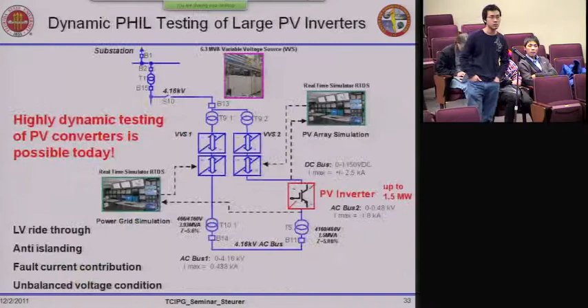If you utilize standard protocols that the utility community uses, and RTDS has provided interfaces for, such as DNP, Modbus, or 61850, then it's a matter of getting the respective I/O cards for the RTDS and having the counterpart in the real-time network simulator. We also experiment with customized protocols developed on dedicated FPGA platforms that tie seamlessly into the RTDS. I think the interface is one of the major challenges one may face, and then of course the expertise in this regime, which you guys clearly have a head start on.